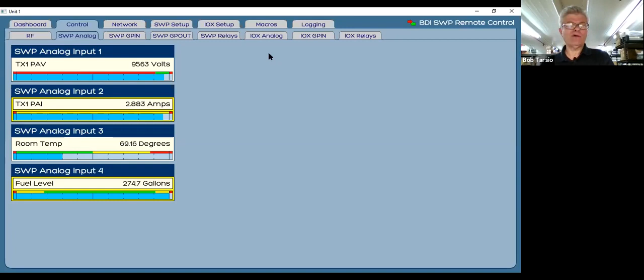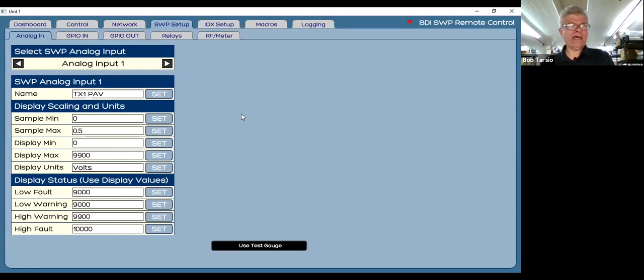The IOX analog, if you want to go into the setup here, to show you how we set these up. Here's an analog input, this is channel 1. If I bring this up, I can do a test gauge. You'll notice over here on the right there's an A to D converter. This is the actual voltage of the sample that's being fed to that A to D input. So I'll clear it out and put that back in, 483, and that tells the unit that's the actual sample.